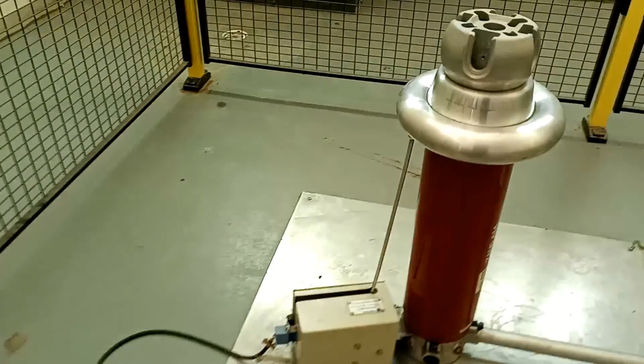One of the major components we have here is the earthing switch. Once we conduct the experiment and switch off, this switch will be connected to the equipment such that whatever residual high voltage is present on the equipment will be discharged through the earth, through the earthing rod.